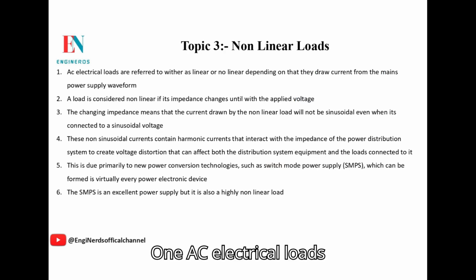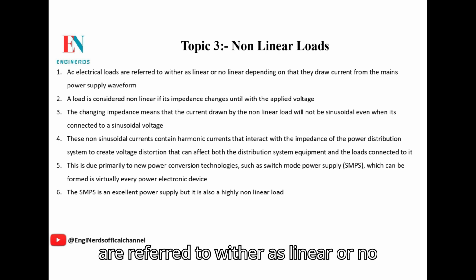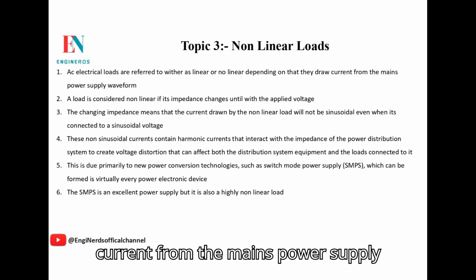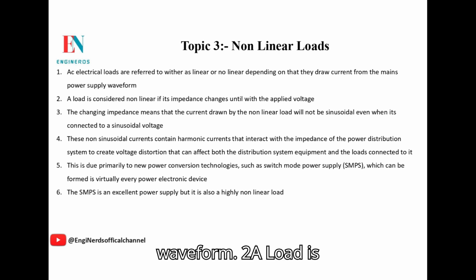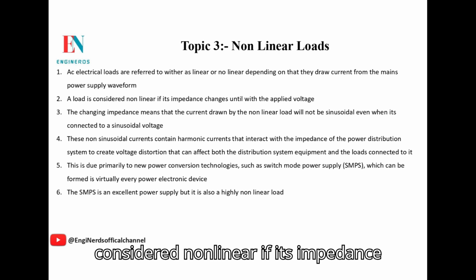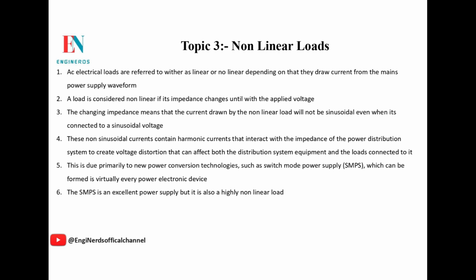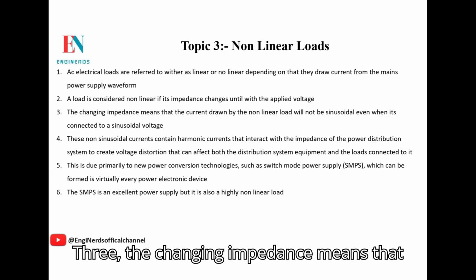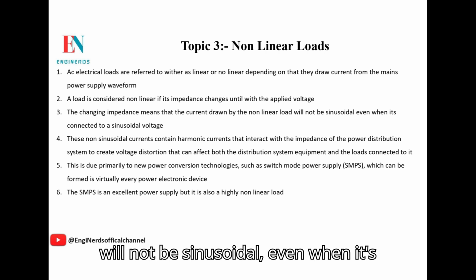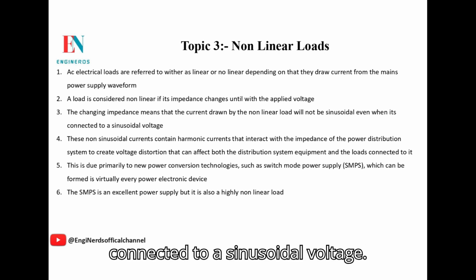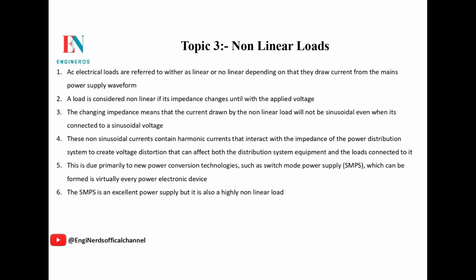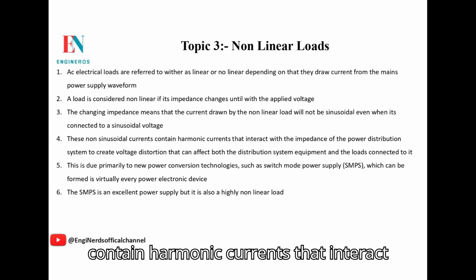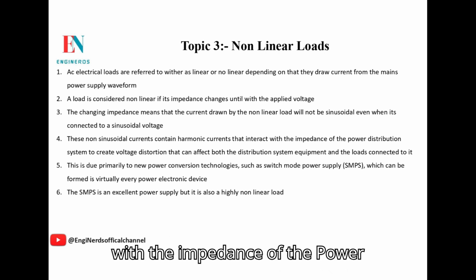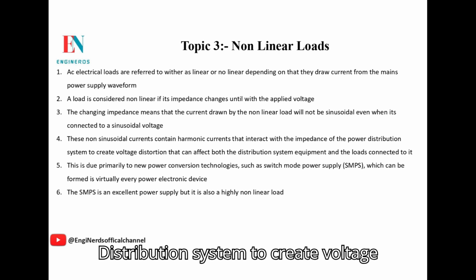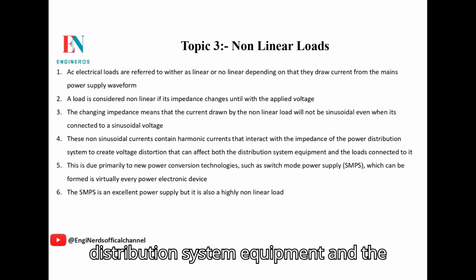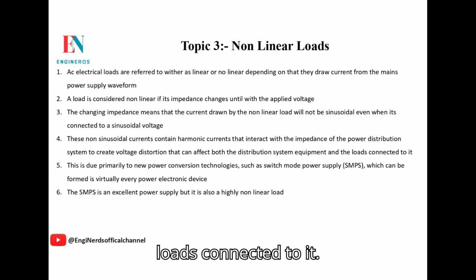1. AC electrical loads are referred to as either linear or nonlinear depending on how they draw current from the mains power supply waveform. 2. A load is considered nonlinear if its impedance changes with the applied voltage. 3. The changing impedance means that the current drawn by the nonlinear load will not be sinusoidal even when it is connected to a sinusoidal voltage. 4. These non-sinusoidal currents contain harmonic currents that interact with the impedance of the power distribution system to create voltage distortion that can affect both the distribution system equipment and the loads connected to it.